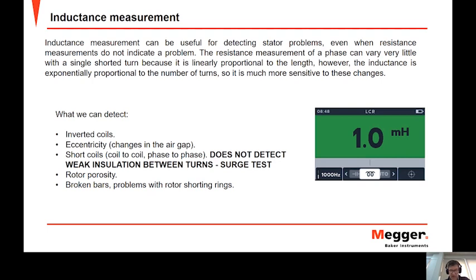I saw a case a few years ago with a salient pole generator rotor. I measured the 4 coils separately, and the 4 coils had very similar resistance values. I then measured the coils using the inductance test, and one of the 4 coils had a vastly different value, and it was hence faulty. So resistance doesn't always show you the problem.